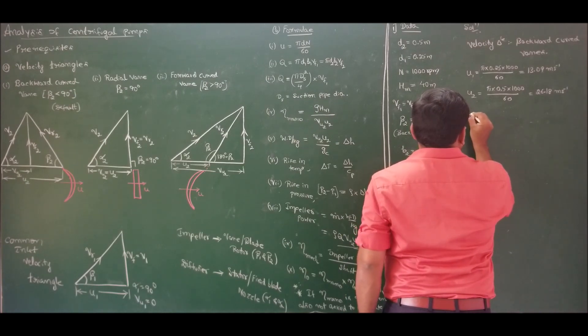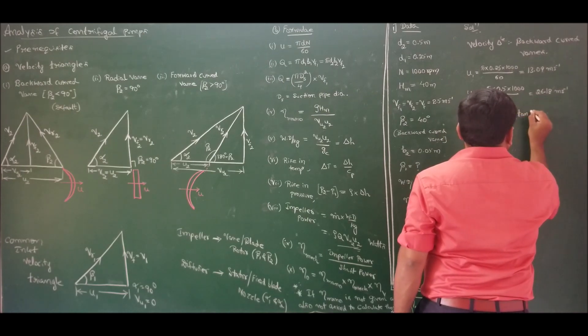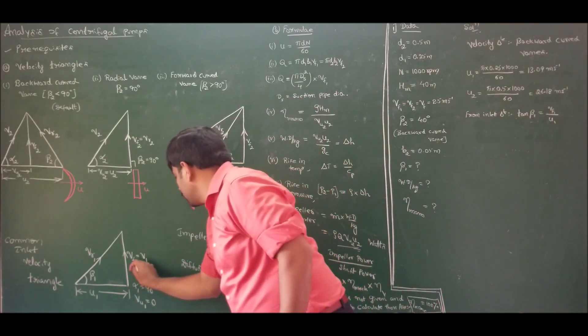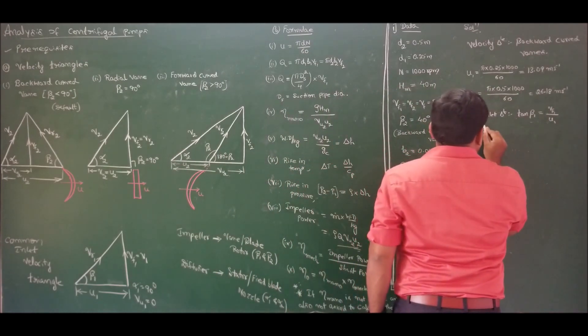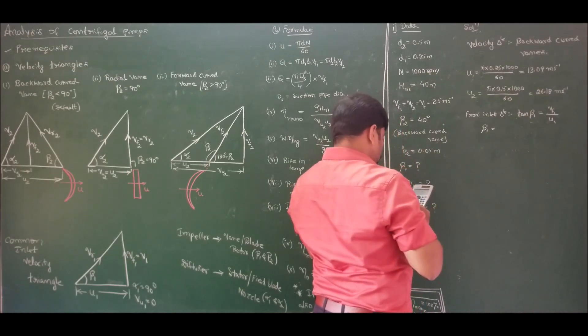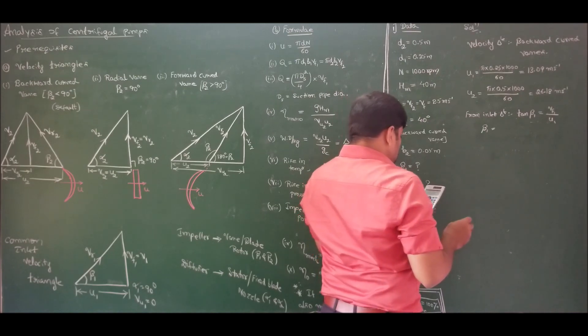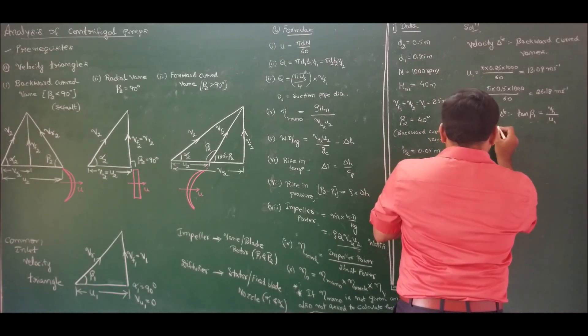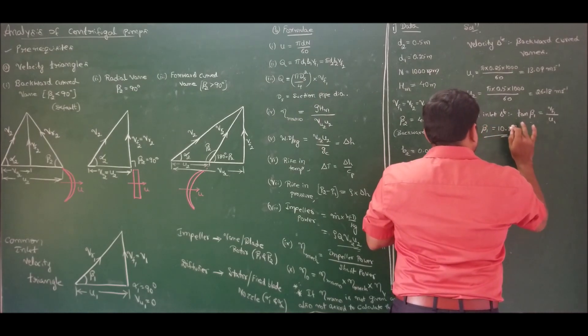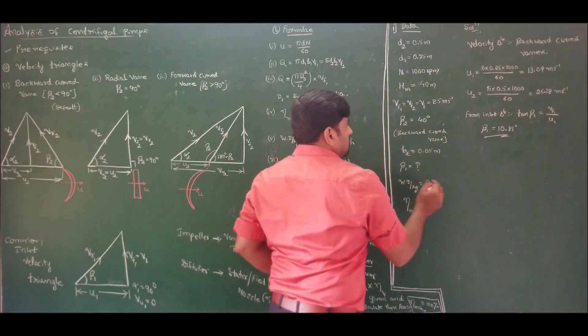From the inlet velocity triangle, taking tan(beta1) = Vf1 / U1, we get beta1 = tan⁻¹(2.5 / 13.09) = 10.81 degrees. So we have calculated the first required quantity — vane angle at inlet, beta1 = 10.81 degrees.